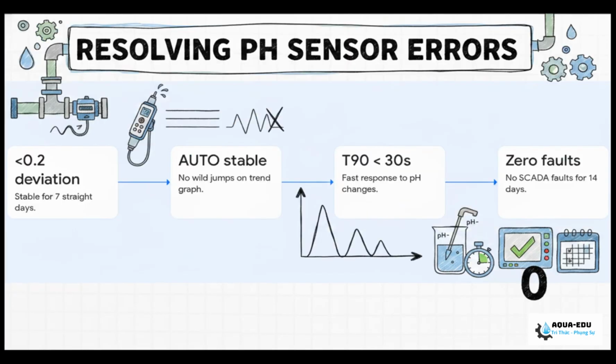We only declare the incident fully closed and resolved when we hit these exact success criteria. We need to see less than a 0.2 deviation between the online sensor and the handheld for 7 straight days. The auto-dosing mode must remain perfectly stable, no wild jumps on the trend graph. The probe's T90 response time, which just means how fast it reacts to a pH change, has to be under 30 seconds, and we want absolutely 0 SCADA faults for 14 straight days.